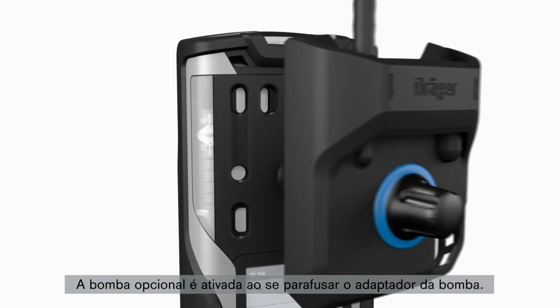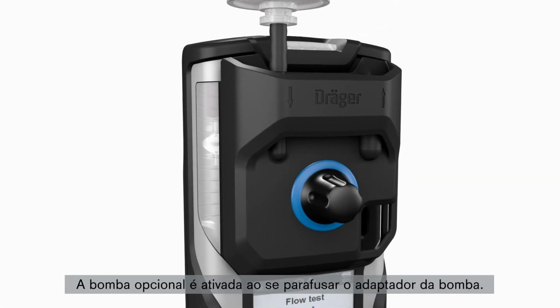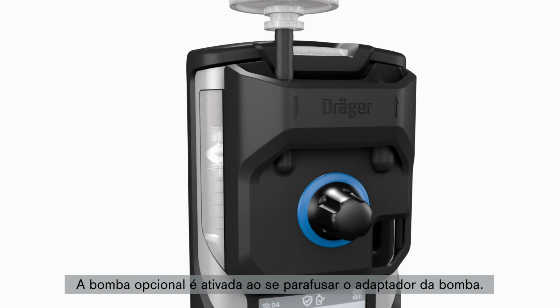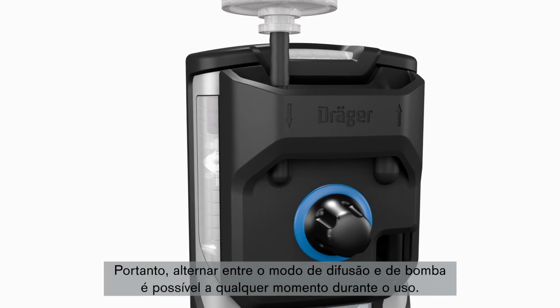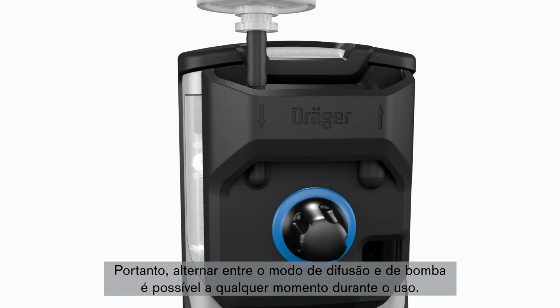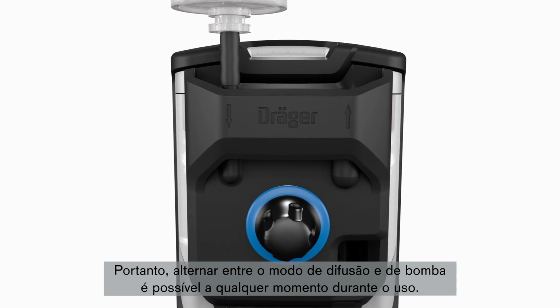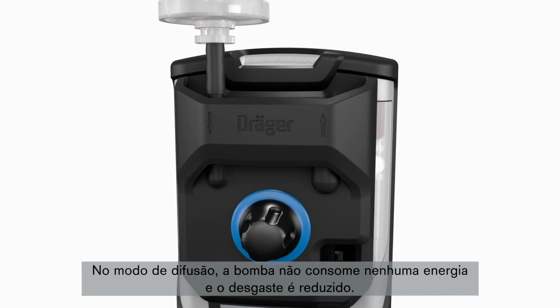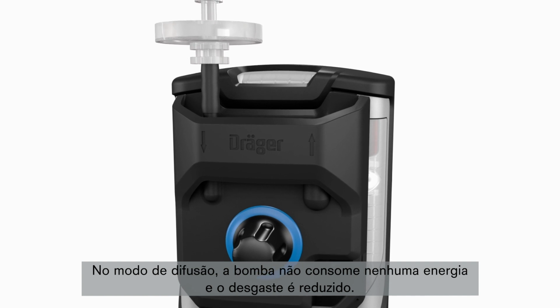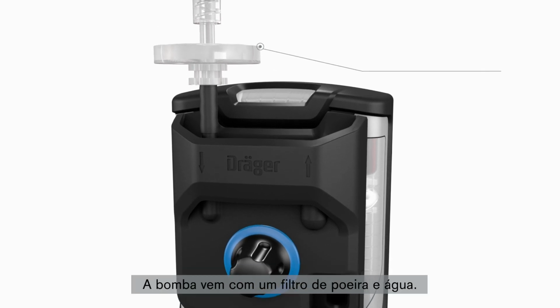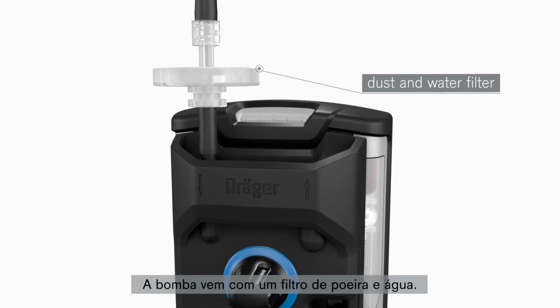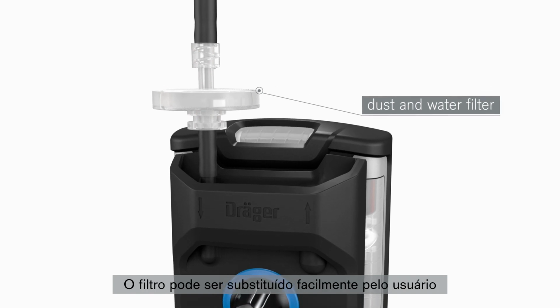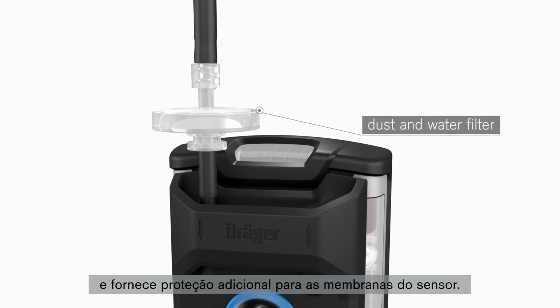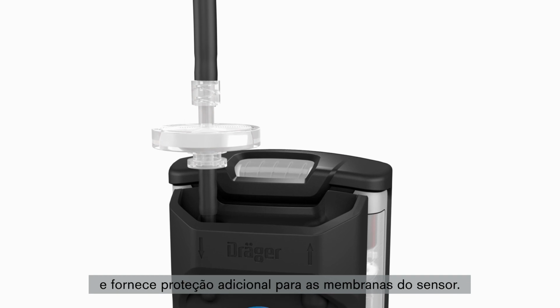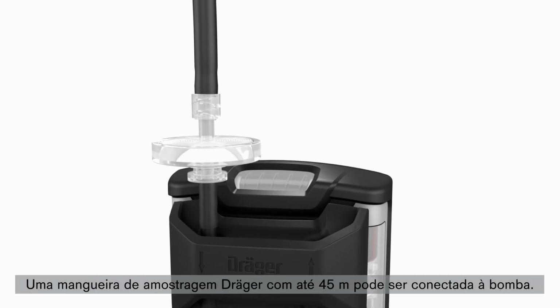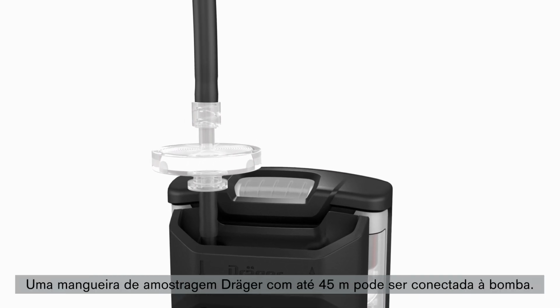The optional pump is activated by simply screwing on the pump adapter. Toggling between diffusion and pump mode is therefore possible at any time during use. In diffusion mode, the pump does not consume any power and pump wear is reduced. The pump is equipped with a dust and water filter. The filter can easily be replaced by the user and provides additional protection for the sensor membranes. A Dräger sampling hose of up to 45 meters in length can be connected to the pump.